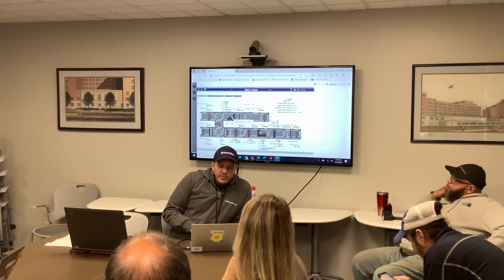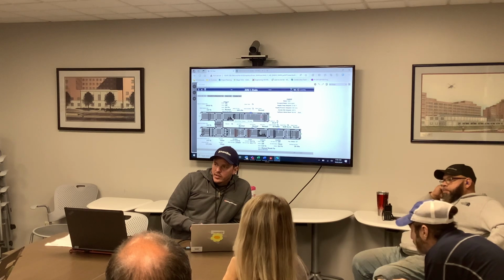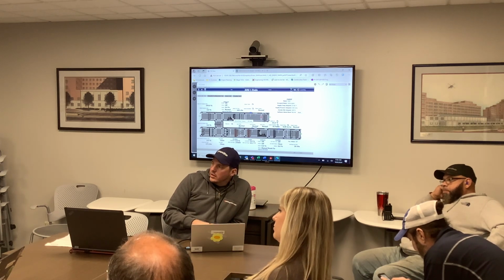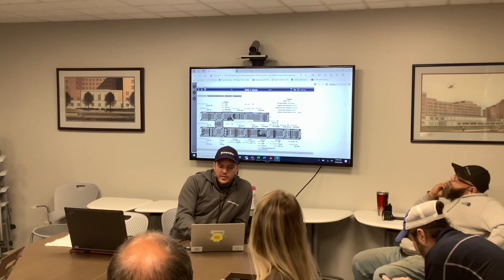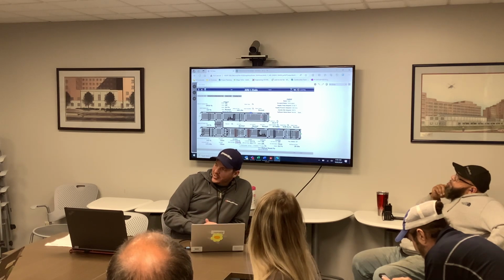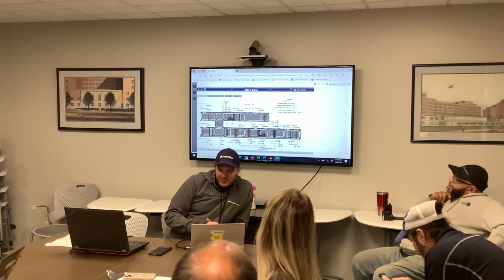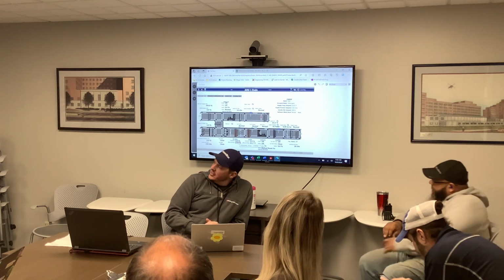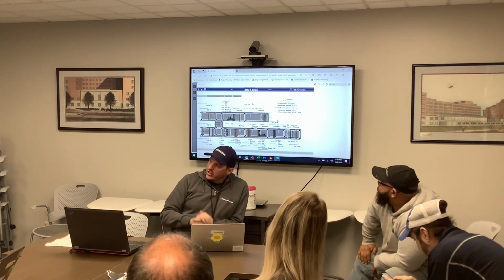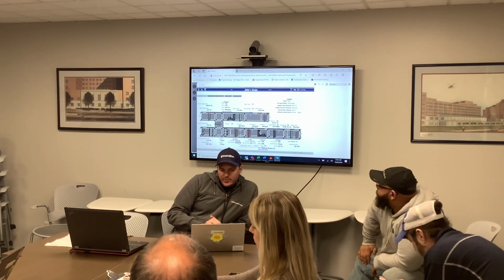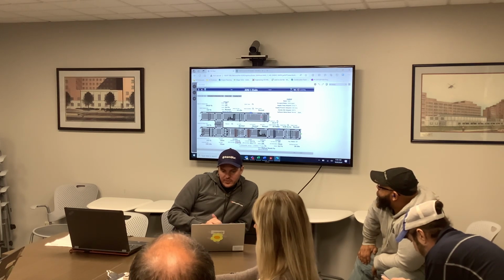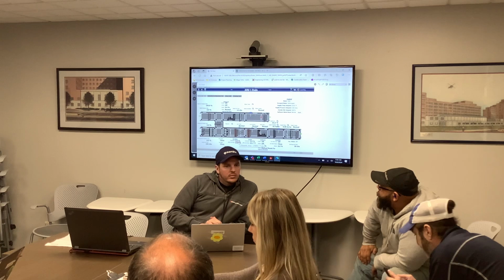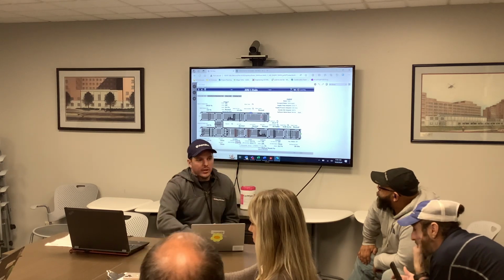Alright, I think that's what I got for you guys on the front end. Do you guys have any questions or anything? Is that temp sensor going to get fixed right there, after the heating coil? After heating coil? It's a great question, I don't know yet. There's actually no space for it. The coils are like touching each other. Gotcha. No, that's not good. So it's the after heating coil, after the preheat coil now.